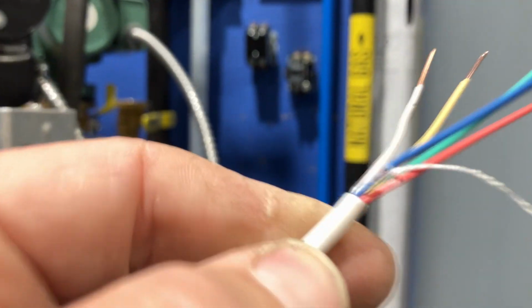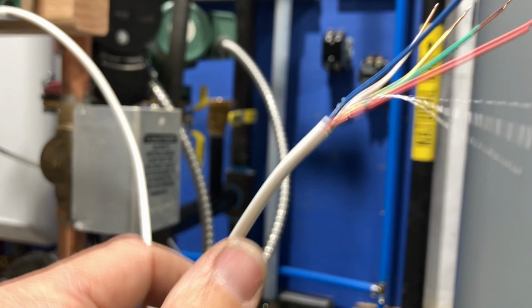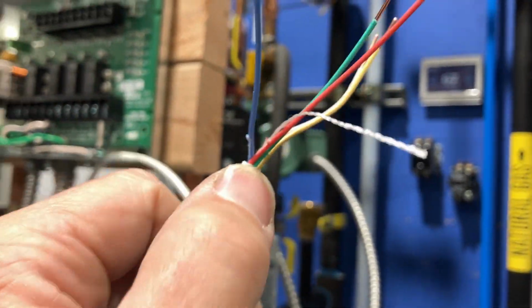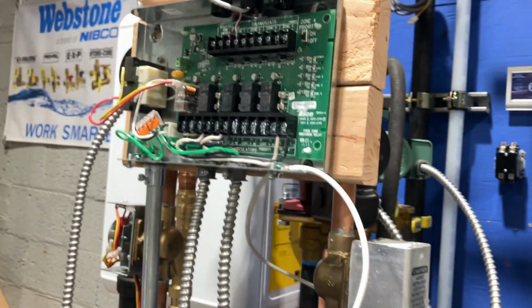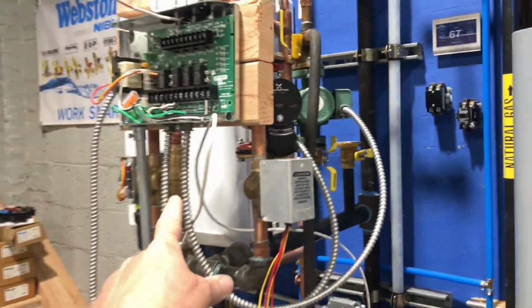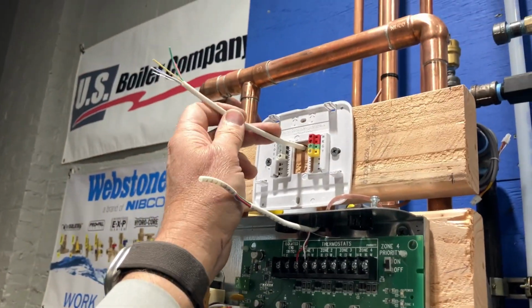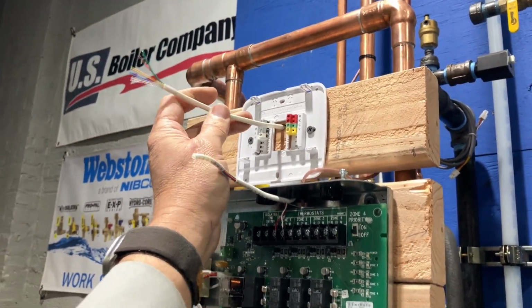When it's a little nick like that, you want to pull back the string, and then you'll cut that away because you don't want to have any shorts there. This wire, don't worry about that for right now. We'll talk about that in a minute. That's going to our boiler. But let's wire in for cooling only. There's only 2 wires we're going to need. And you know what 2 wires those are going to be?